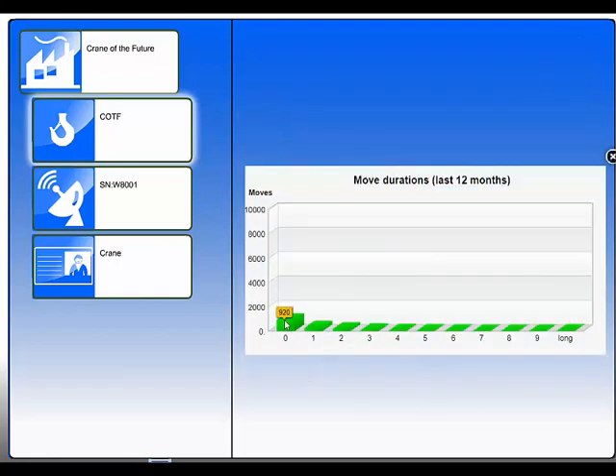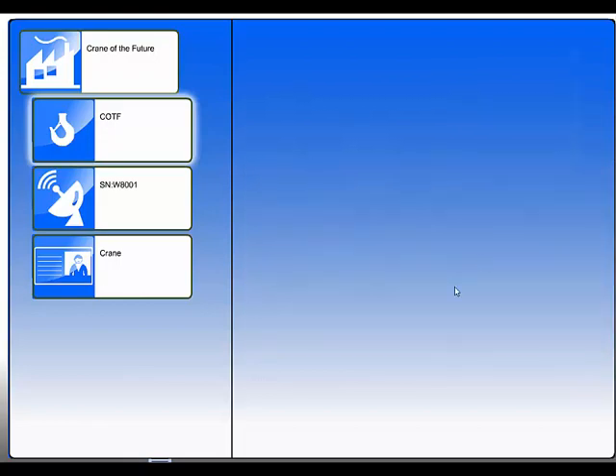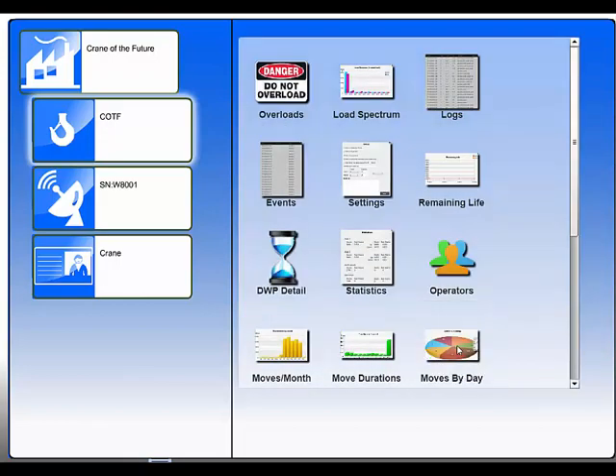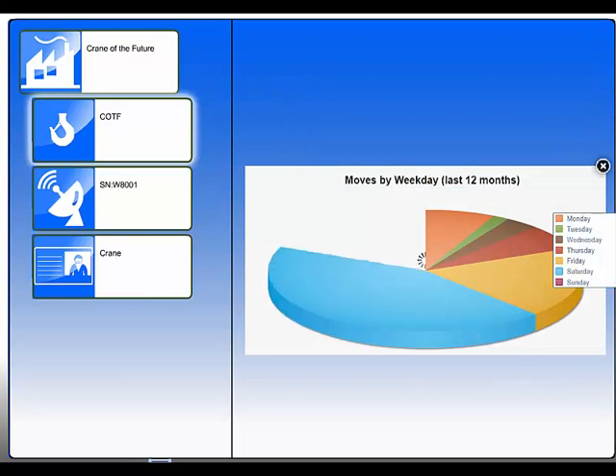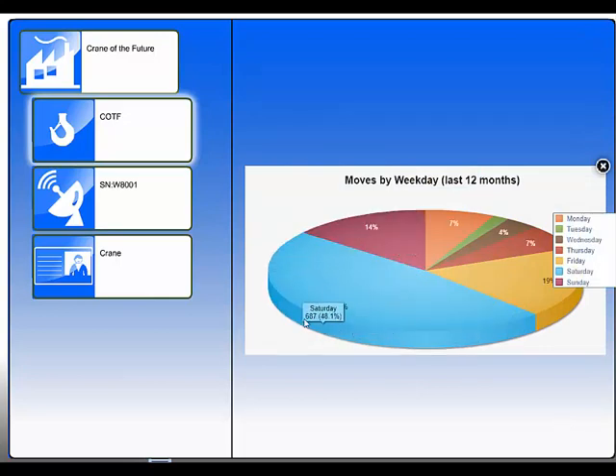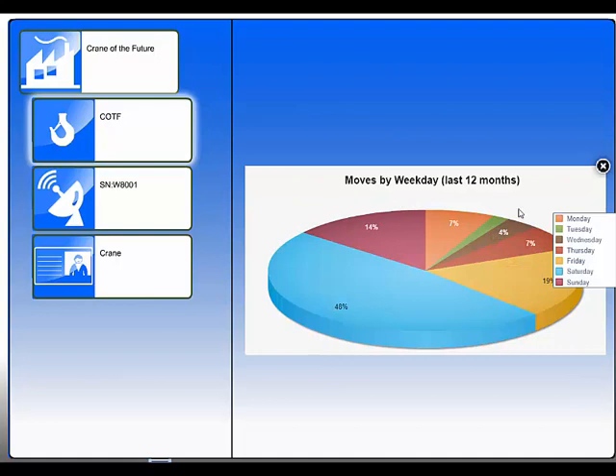This shows you whether or not people are inching the crane too much or whether they're mostly doing long moves. This is a really useful graph if you're finding yourself going through brake linings or contactors a lot. And we can tell if everybody gets busy at the end of the week. Here I was obviously doing a fair bit of demonstration on a Saturday, but it's not unusual to see patterns here which don't reflect what you understand your workflow to be in the organization.